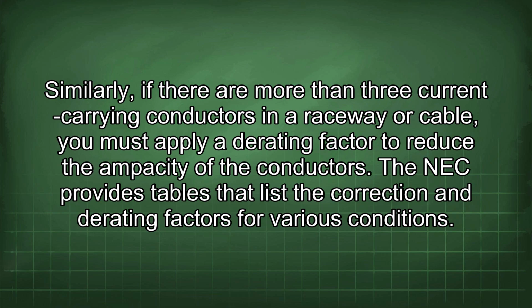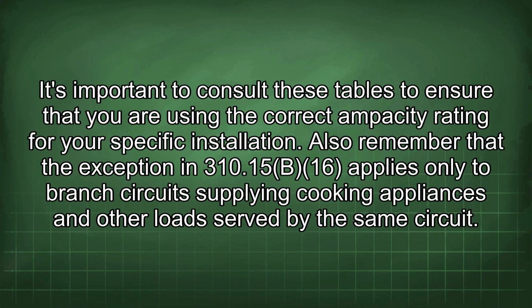Similarly, if there are more than 3 current-carrying conductors in a raceway or cable, you must apply a derating factor to reduce the ampacity of the conductors. The NEC provides tables that list the correction and derating factors for various conditions. It's important to consult these tables to ensure that you are using the correct ampacity rating for your specific installation.